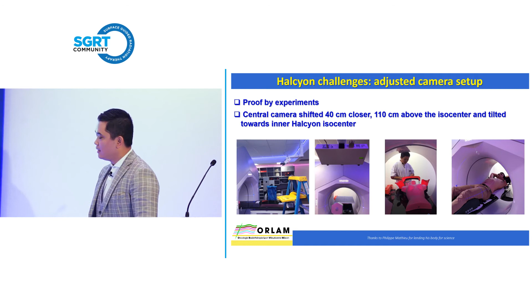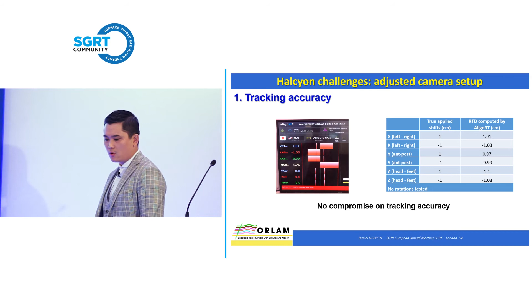So here I want to show you a result inside the bore. Firstly, tracking accuracy: we tried to shift the couch 1 centimeter in every direction. Here we can see we obtain a very good result, so no compromise on tracking accuracy. This is on breast, Philippe, in the breast position. We can see here we didn't see the supraclavicular, chin and arm, and for this case, for head and neck treatment. So we obtain limited visibility even with 5 degrees of breast board of upper torso, arm and chin. So we can say that this setup cannot be used for intracranial and head and neck and breast treatment.